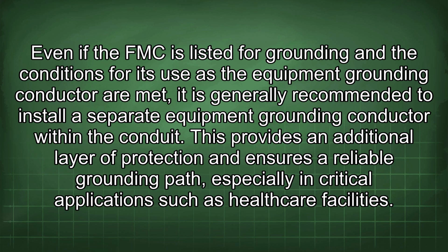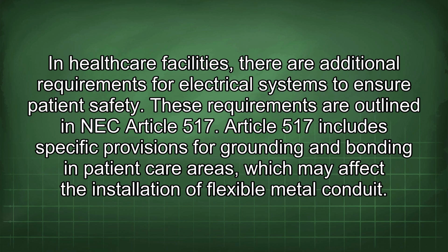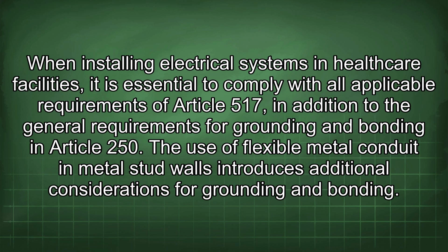This provides an additional layer of protection and ensures a reliable grounding path, especially in critical applications such as healthcare facilities. In healthcare facilities, there are additional requirements for electrical systems to ensure patient safety. These requirements are outlined in NEC Article 517. Article 517 includes specific provisions for grounding and bonding in patient care areas, which may affect the installation of flexible metal conduit. When installing electrical systems in healthcare facilities, it is essential to comply with all applicable requirements of Article 517, in addition to the general requirements for grounding and bonding in Article 250.